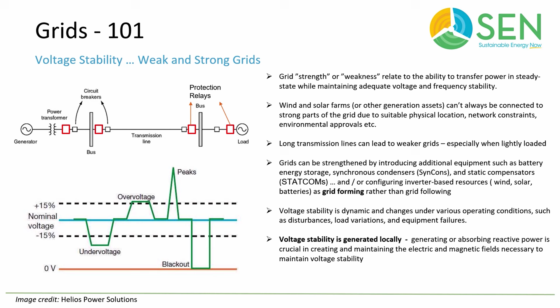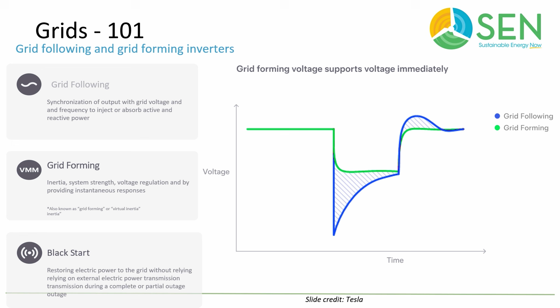Quickly, on a piece of technology, you may have heard about grid following and grid forming inverters. Grid following inverters, as you can probably imagine, synchronize with the grid and inject current into an existing grid. They are unable to operate independently when disconnected from the grid in an islanded mode, but in your household, a battery and a hybrid inverter can still operate to power your house if the grid does drop out. Grid forming inverters, by contrast, actually create their own voltage and frequency to help control the grid, enabling islanded operation, black start capability, and increased stability. They can't be used universally, unfortunately, because some parts of the grid can be what's called stiff, which has high strength that resists changes in voltage and frequency, I should say. But modern inverters are capable of switching between those two modes.